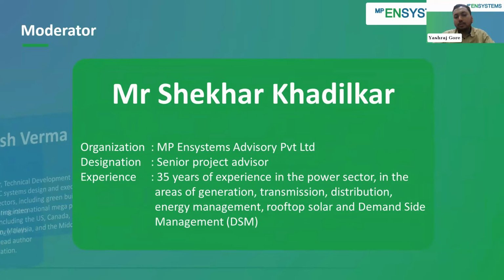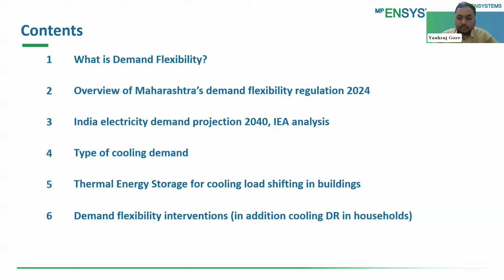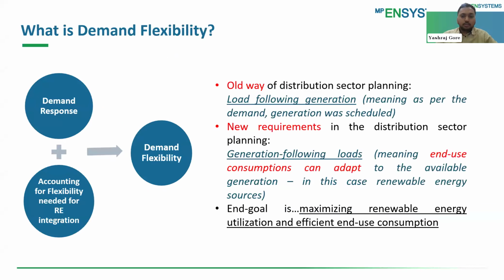Briefly, I want to talk about the demand flexibility concept and the importance of cooling demand in managing grid operations. This is the flow of my short presentation. In the historical trend, we had load following generation, which mainly means that you have the fixed demand, and you have the generation capacity which needs to be modulated according to the demand which is there.